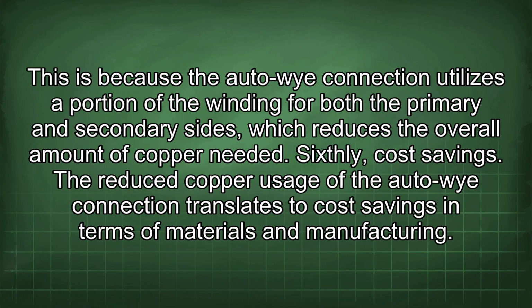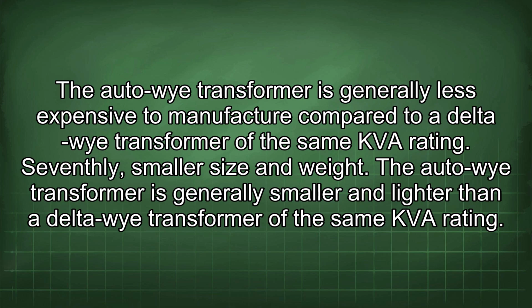This is because the Auto-Wye connection utilizes a portion of the winding for both the primary and secondary sides, which reduces the overall amount of copper needed. Sixthly, cost savings. The reduced copper usage of the Auto-Wye connection translates to cost savings in terms of materials and manufacturing. The Auto-Wye transformer is generally less expensive to manufacture compared to a delta-Y transformer of the same kVA rating.